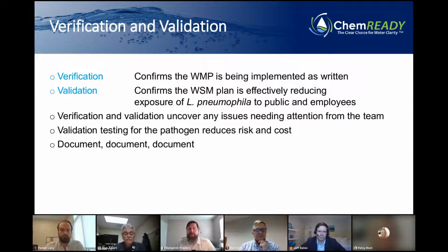The validation step is where the CMS memo caused some confusion back in 2018. Validation means it's effectively reducing the exposure of Legionella pneumophila to the public and employees - that you're reducing the risk of bacteria growth in your system. Examples include control measures like taking temperatures and flushing lines, but the only way to validate those measures are effective is to test for Legionella. You can say your residual chlorine levels have been good all year, or your temperature limits have been in spec, but you don't know if those are effective control measures unless you test for Legionella. The only true way to validate a plan is Legionella testing.